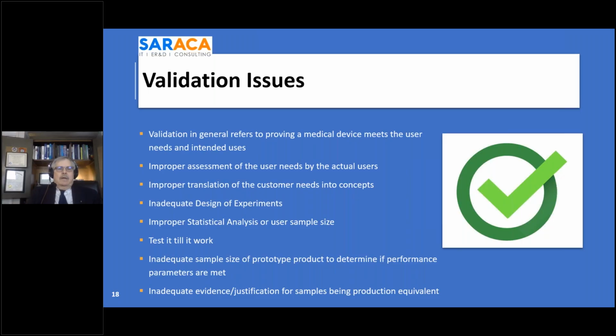Validation issues. I'm just going to cover this briefly. Validation in general refers to proving a medical device meets the user needs and the intended use. This goes along with making sure that you're validating to ensure that your device meets its performance specifications. That's very important. This has become a huge issue. You can do validation, you can put the device out in the field, and it doesn't meet the user needs, and therefore it's not essential performance. That's critical. Important is proper assessment of the user needs by the actual users.